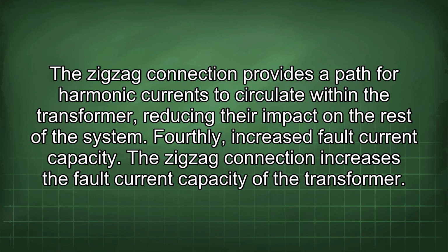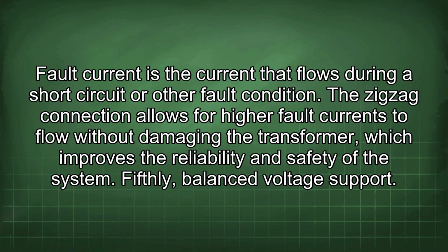Fourthly, increased fault current capacity. The zigzag connection increases the fault current capacity of the transformer. Fault current is the current that flows during a short circuit or other fault condition. The zigzag connection allows for higher fault currents to flow without damaging the transformer, which improves the reliability and safety of the system.